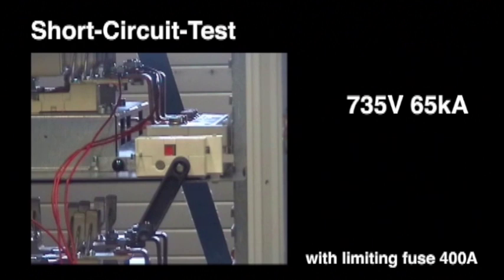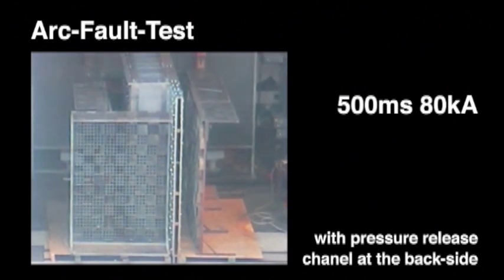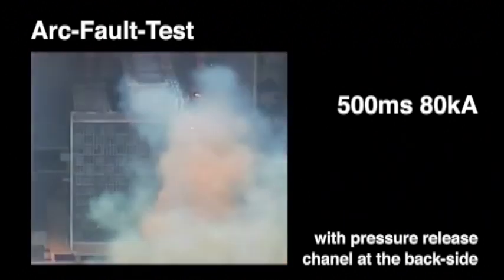The special construction of the complete system allows the installation of an internal arc fault exhaust duct at the backside of the switchboard panel. An arc fault test of 80 kiloampere for 500 milliseconds has been successfully passed.